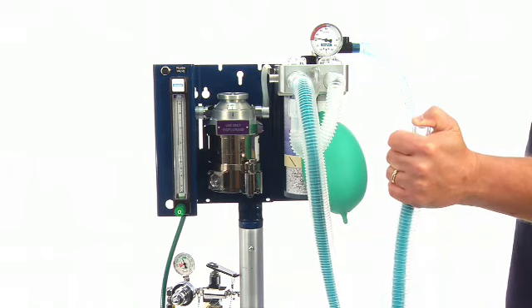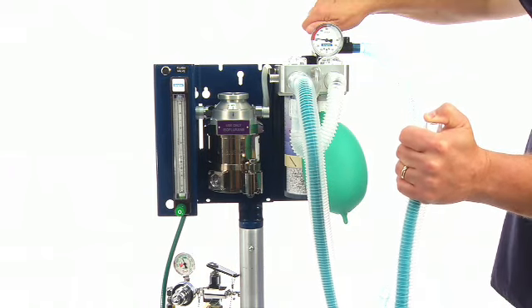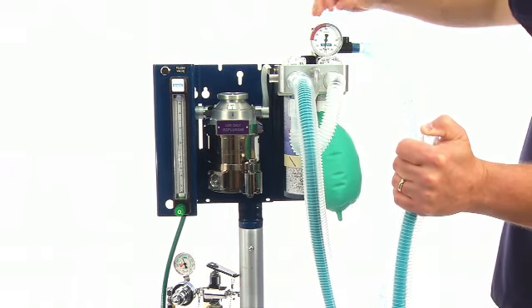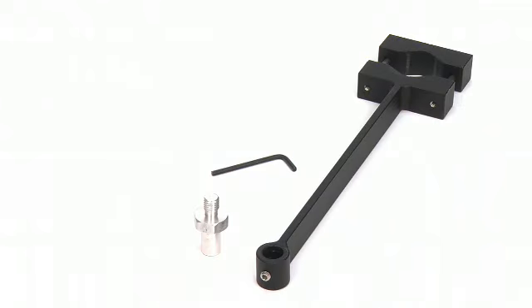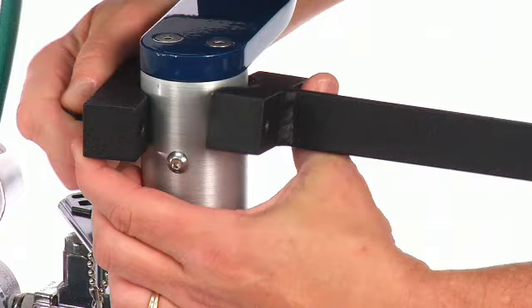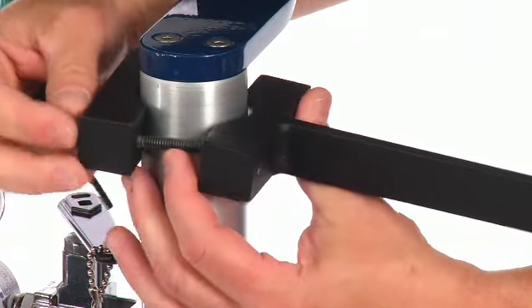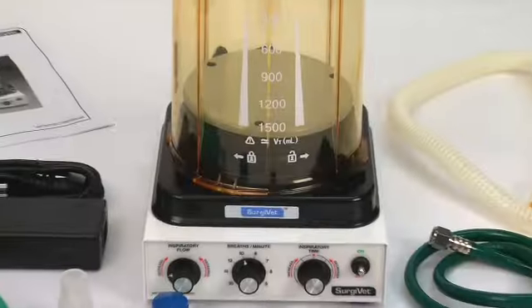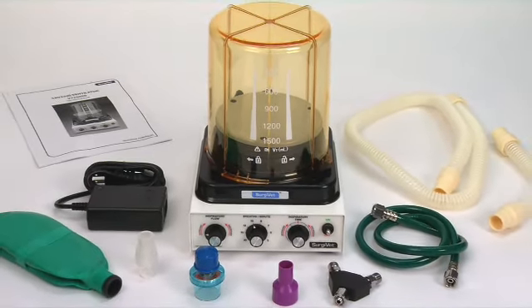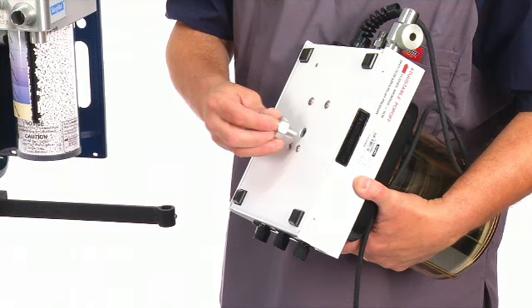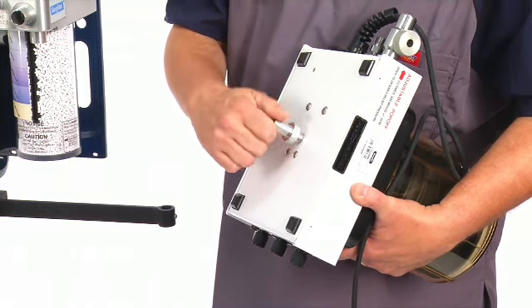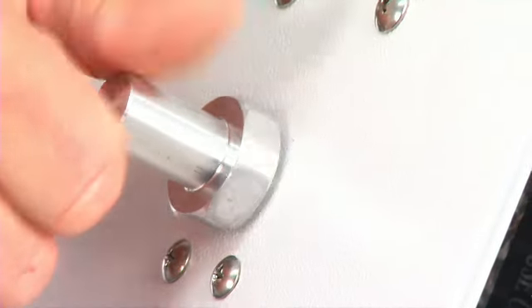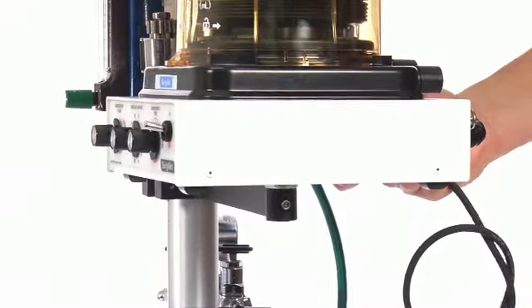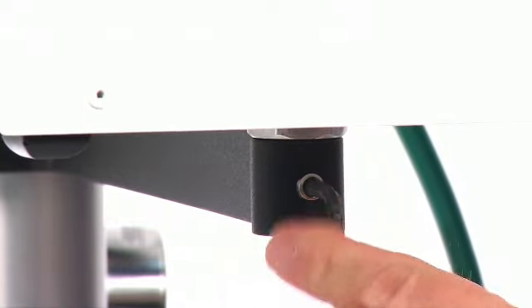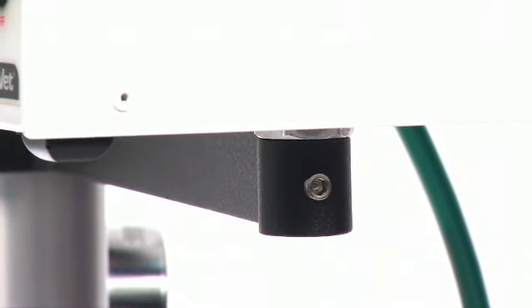Once the anesthesia machine is pressure tested and leak-free, you can connect the SAV2500 ventilator. There is an optional universal ventilator mounting bracket that can be used to mount the ventilator to a pole-style anesthesia machine. The ventilator is supplied with all required accessories. Attach the bracket stem to the bottom of the ventilator. Insert the bracket stem onto the mounting bracket and secure by tightening the set screw.